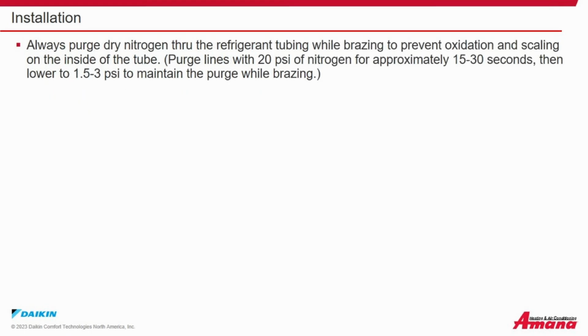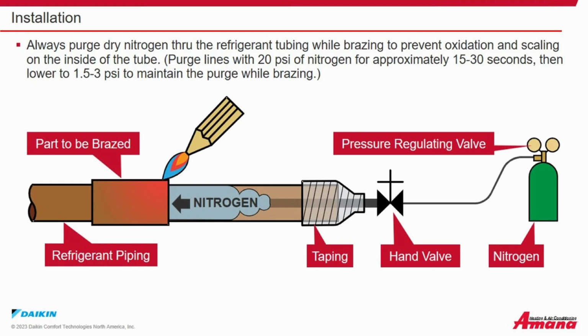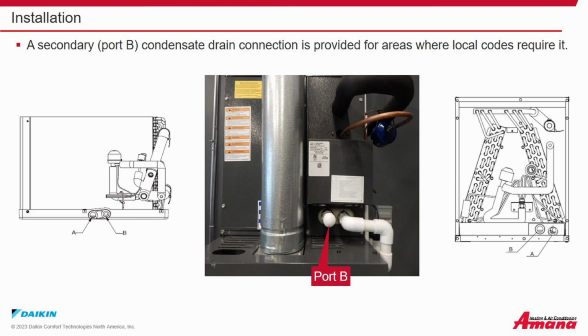Always purge dry nitrogen through the refrigerant tubing while brazing to prevent oxidation and scaling on the inside of the tube. Purge lines with 20 psi of nitrogen for approximately 15 to 30 seconds. Then lower the pressure to 1.5 to 3 psi to maintain the purge while brazing. A secondary, or Port B, condensate drain connection is provided for areas where local codes require it.